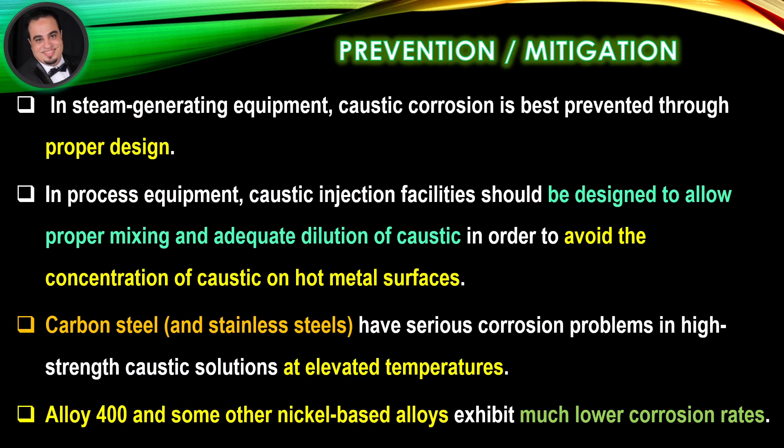Prevention and mitigation: In steam generating equipment, caustic corrosion is best prevented through proper design. In process equipment, caustic injection facilities should be designed to allow proper mixing and adequate dilution of caustic, in order to avoid the concentration of caustic on hot metal surfaces. Carbon steel and stainless steels have serious corrosion problems in high-strength caustic solutions at elevated temperatures. Alloy 400 and some other nickel-based alloys exhibit much lower corrosion rates.